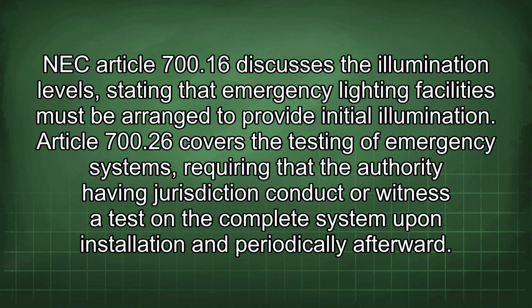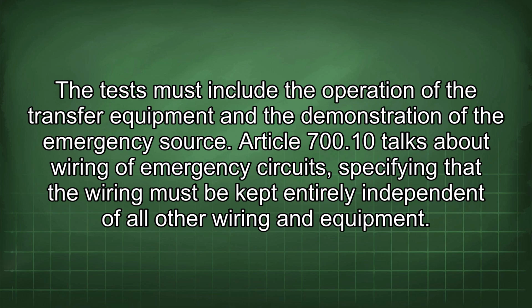Article 700.26 covers the testing of emergency systems, requiring that the authority having jurisdiction conduct or witness a test on the complete system upon installation and periodically afterward. The test must include the operation of the transfer equipment and the demonstration of the emergency source.